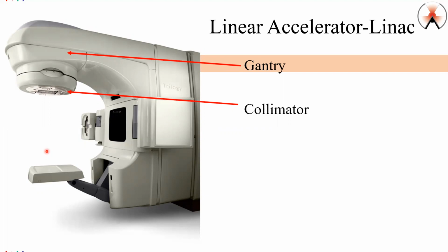The machine is calibrated to rotate about that isocenter, and the distance from that isocenter to the source of the radiation is 100 centimeters. Okay? So we put the patient relative to that isocenter. We move that patient, that couch, everything in that room relative to this isocenter.